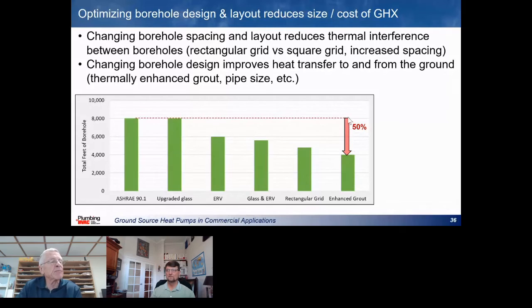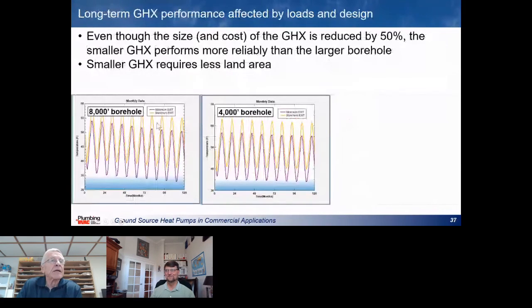Which one is the client most likely to buy? And what's even more interesting is that this one cools off less over time than a borehole field that's much larger. So you're looking at knocking off 4,000 feet of drilling times, let's say $30 a foot, 120,000 bucks, and you can buy a lot of window and a lot of energy recovery ventilation system for a 23,000 square foot building for that kind of thing. So those are the kinds of trade-offs that we're looking for when we're designing a geothermal system.